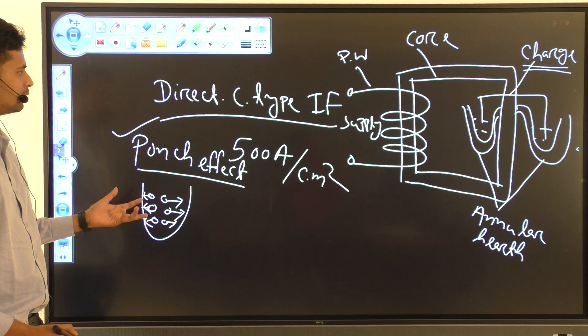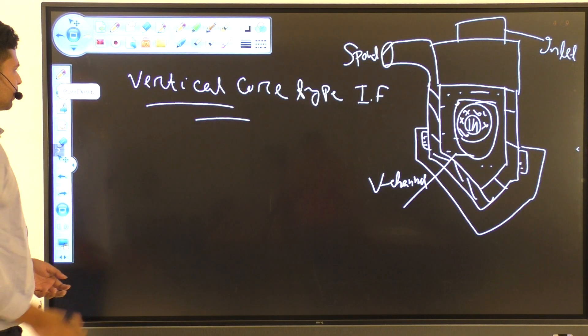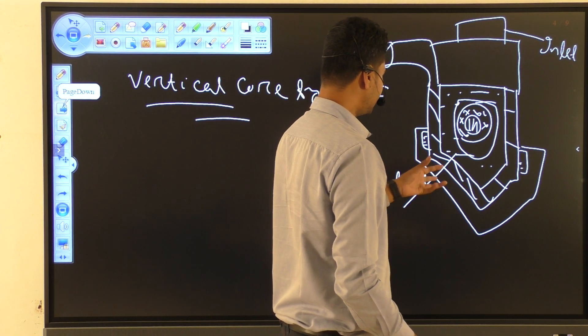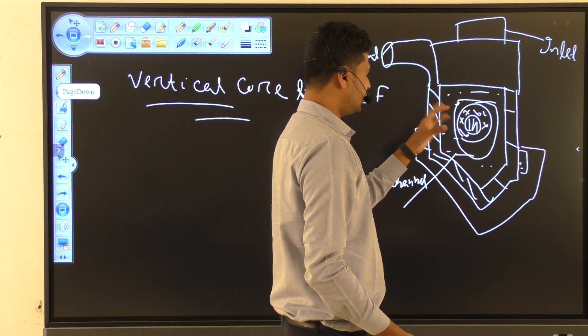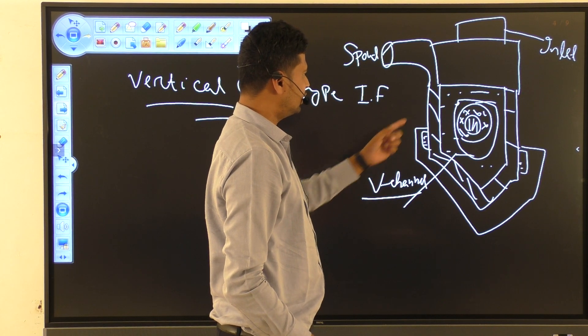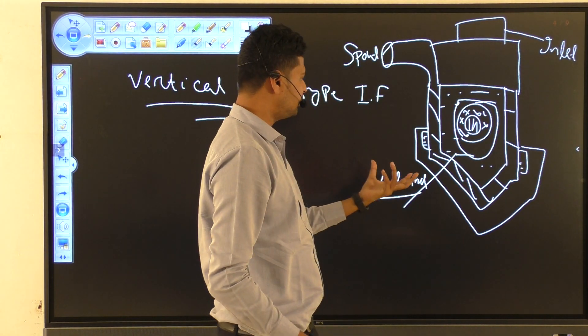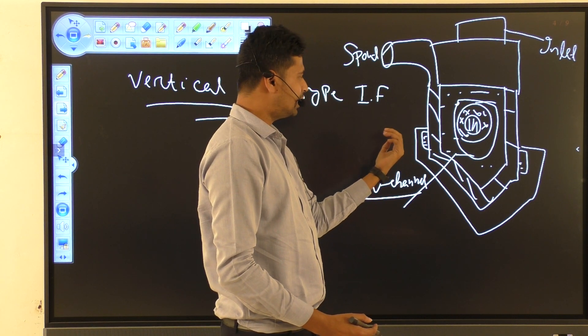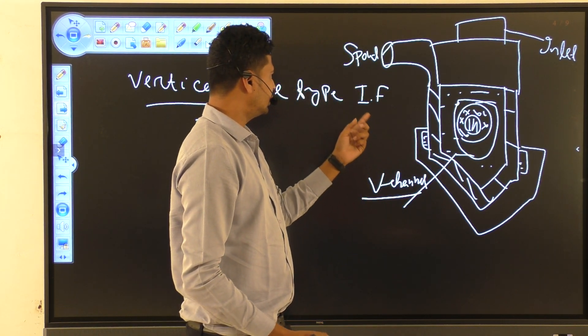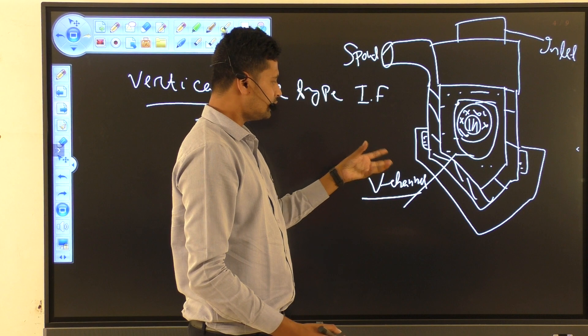This overflow is the biggest demerit of the direct core type induction furnace. Now let's discuss the vertical core type induction furnace. In this furnace, the charge is melted in a V-channel. The charge is input through an inlet and extracted through a spout. A key benefit is that the furnace can be tilted for easy pouring or extraction of the molten metal, and this tilting process is done hydraulically.